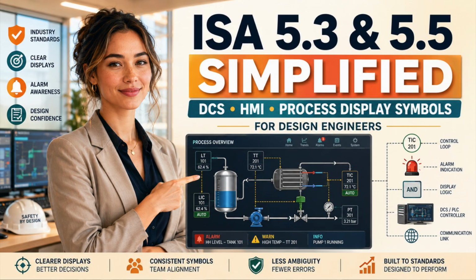A strong process display separates static structure from dynamic behavior. Equipment, lines, and permanent labels provide context. Measurements, equipment states, alarms, control modes, sequence steps, and communication quality reveal what the plant is doing now. Dynamic information must be easier to find than static artwork. A beautifully rendered vessel must never compete visually with rising pressure. A three-dimensional pump must never overpower its trip state. Decorative animation must never distract from a failing process variable. Normal operation should appear calm. Abnormality should create contrast.